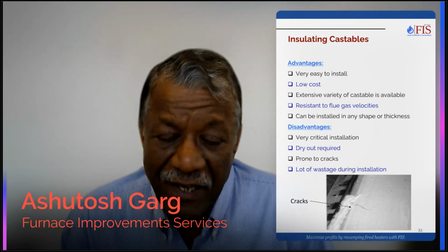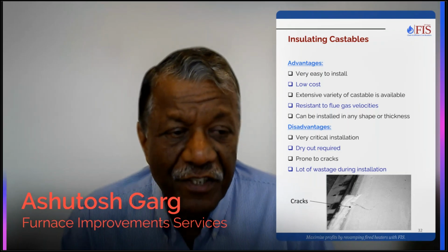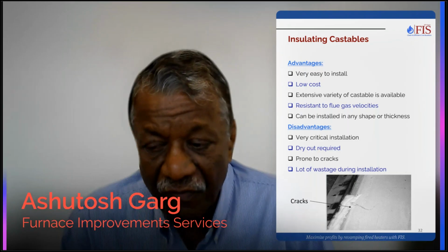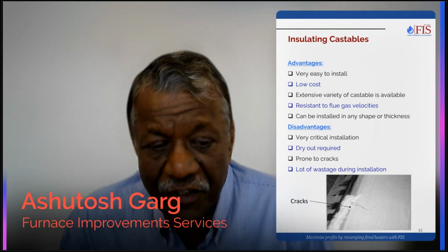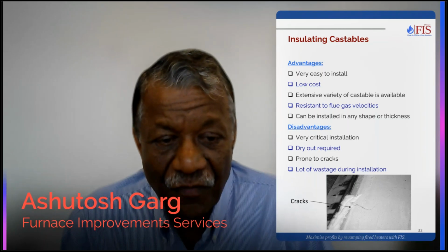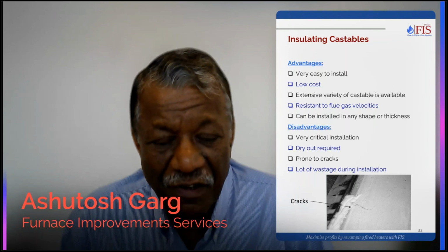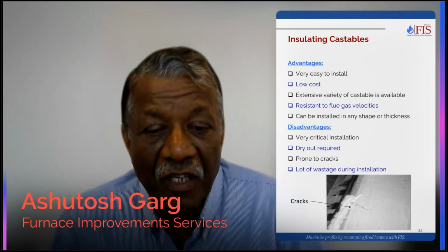It's prone to cracks, and also there is a lot of wastage during installation. In the US, most of the castable is applied using gunning, and there is almost 50% wastage which takes place, which is due to rebounds. It is faster, but it does get wasted.